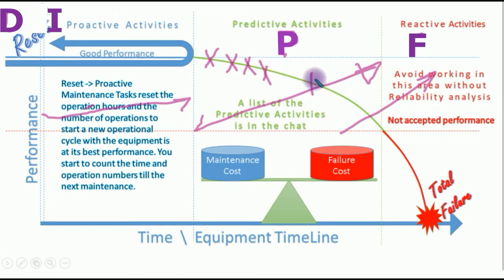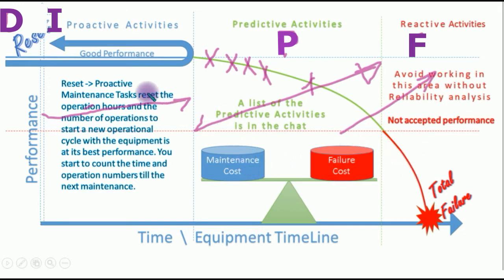This curve is intended to help you understand that in this region, when you work totally blindly without any predictive activity or inspection, you are making a balance between the maintenance cost and the failure cost, because failure is costly — sudden stoppage of the equipment, loss of production time, loss of production material, cascaded failures, and so on. The failure cost is high. So you don't need to invest too much in maintenance changing parts while they are in excellent condition — that's too high a cost. You cannot reach the best practices of maintenance cost by working only in this region.